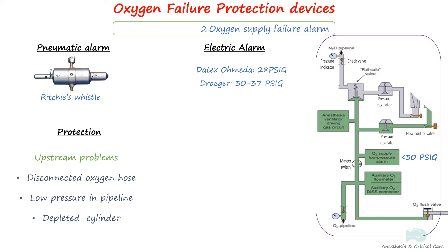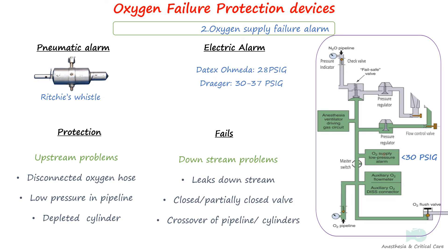These devices do not offer protection against a hypoxic mixture being delivered, as they do not prevent anesthetic gas from flowing if there is no flow of oxygen. Equipment problems like leaks, operator errors like closed or partially closed valves, and accidental crossover on pipeline cylinders are not prevented by this device.